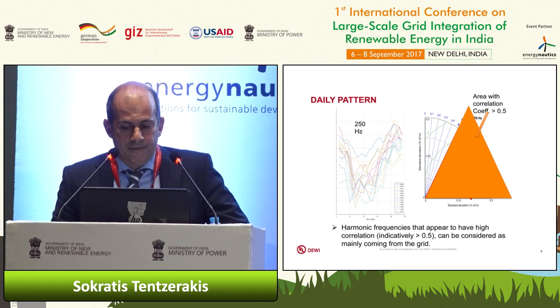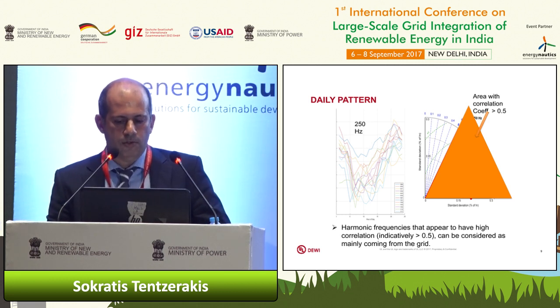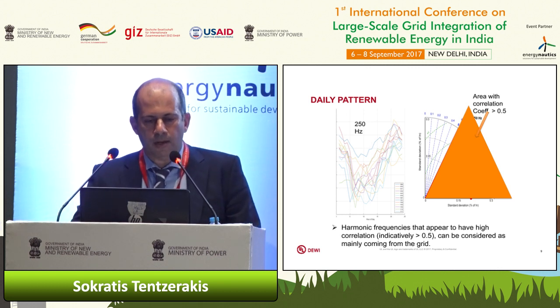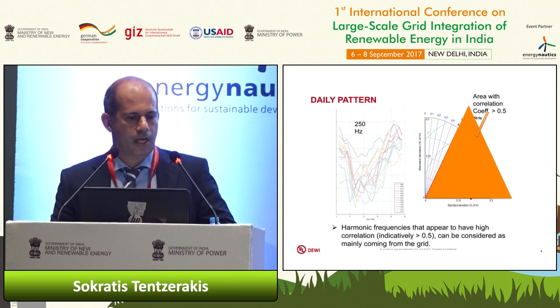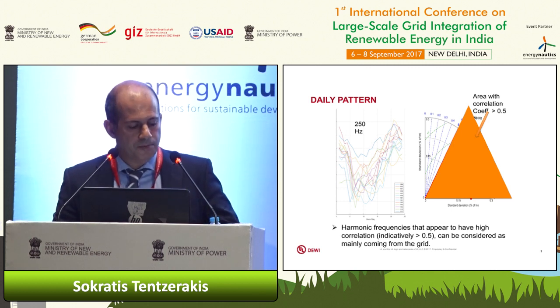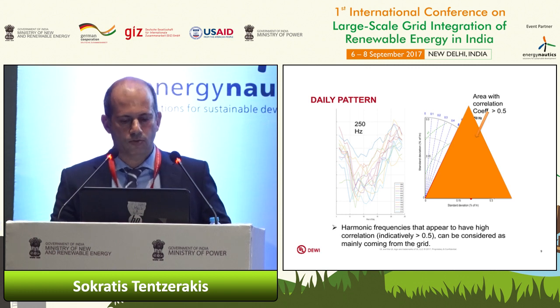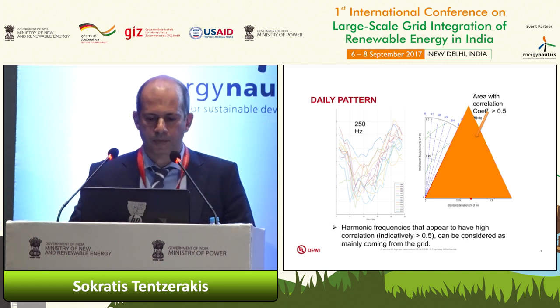So the investigations showed that indeed there are harmonics that have high correlation to each other. That means that they might be coming from the grid, and some other harmonics which are clearly due to the wind turbine have very low correlation.